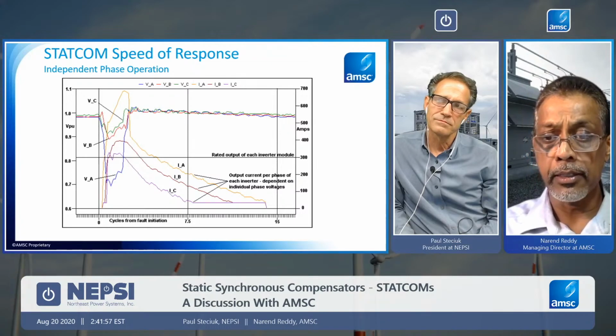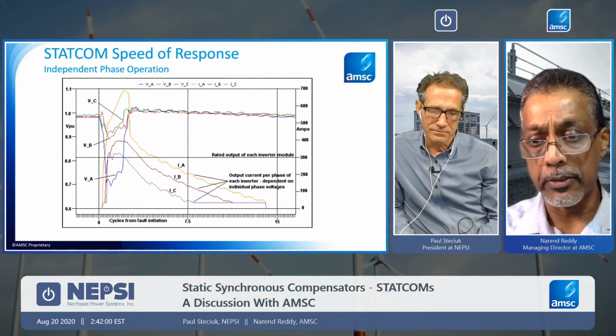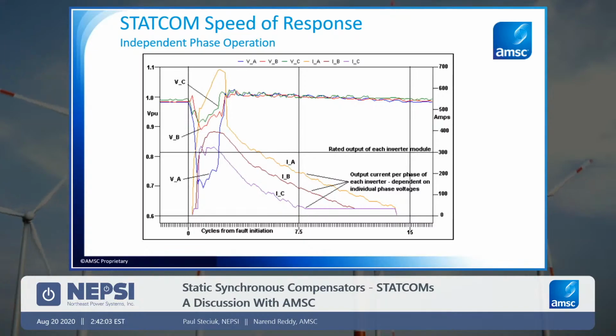I just wanted to make a note here, to show you, when we talked about speed of response, an actual capture of a response characteristic from a STATCOM output for a sag event. As you can see, a couple of things are being shown here. The voltages up above start just under 1 per unit, but then there is a sag, where the time is 0 cycles from fault initiation. At that point, the sag starts. As you can see, that sag is a highly unbalanced sag. The A phase voltage drops to about 70%, where the B and C phases are somewhere around 90% at that time.